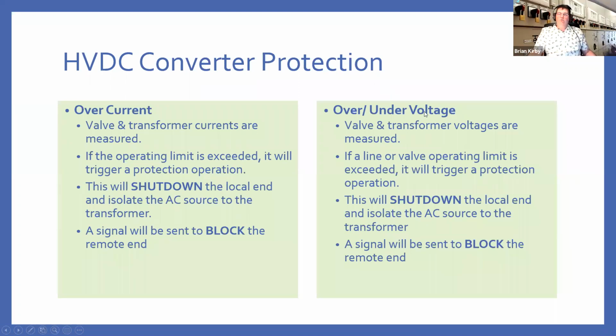Similarly, if you have over or under voltage on your valve and transformer, you will locally shut down and you will send a block to the remote end to isolate this part of the network. If the fault is a transient thing in the local network, you may be able to close it, but typically if it's a fault in the transformer, you will probably have to do some investigations before you re-energize.